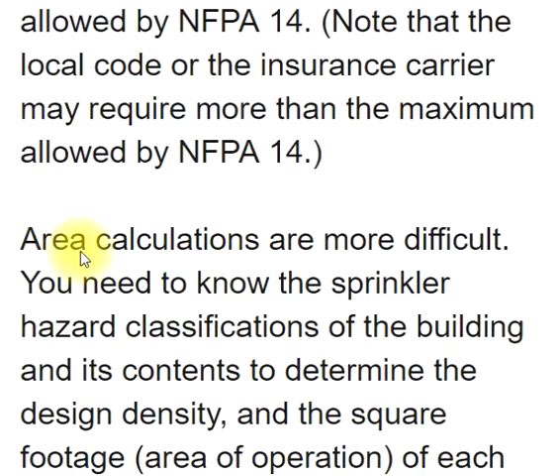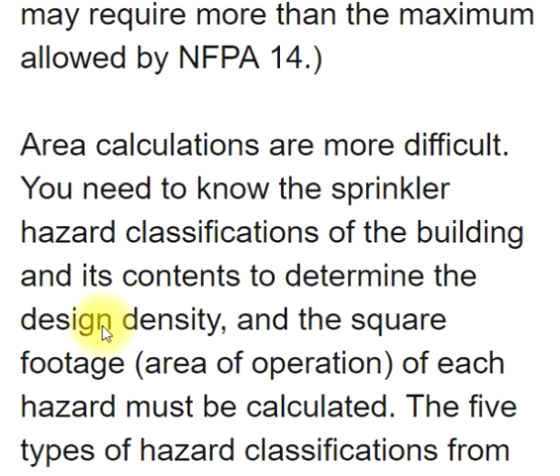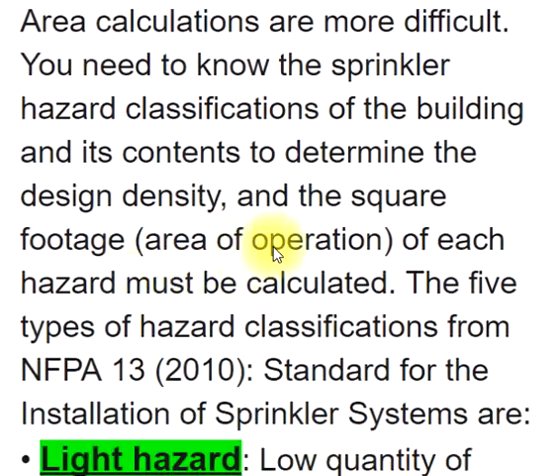Area calculations are more difficult. You need to know the sprinkler hazard classifications of the building and its contents to determine the design density, and the square footage (area of operation) of each hazard must be calculated.